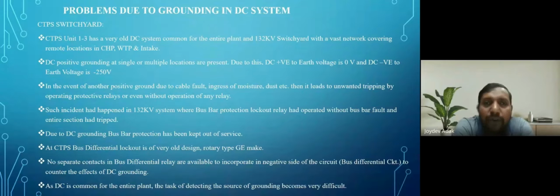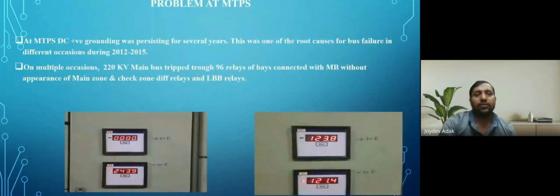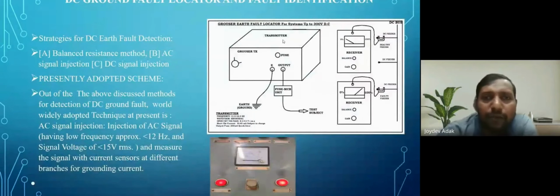For checking DC grounding, the first option was to isolate the DC branches one by one and check which branch is faulty, then isolate the faulty part and normalize the rest. But this was not feasible for a power station, because a power station does not allow shutdown of any branches. That's why we arranged a DC earth fault locator. This is the DC earth fault locator.